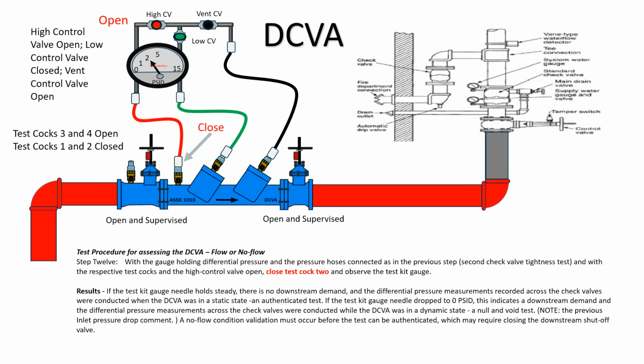Test procedure for assessing the DCVA status, flow or no flow. Step 12. With the gauge holding differential pressure, and the pressure hoses connected as in the previous step, second check valve tightness test, and with the respective test cocks and the high control valve open, close test cock 2, and observe the test kit gauge.